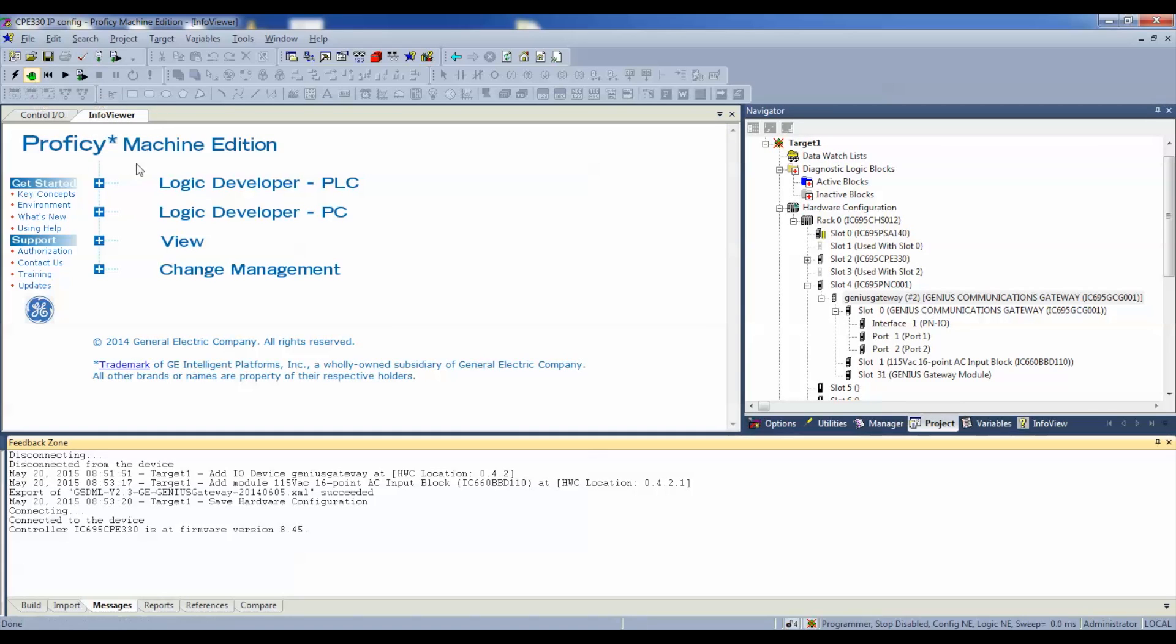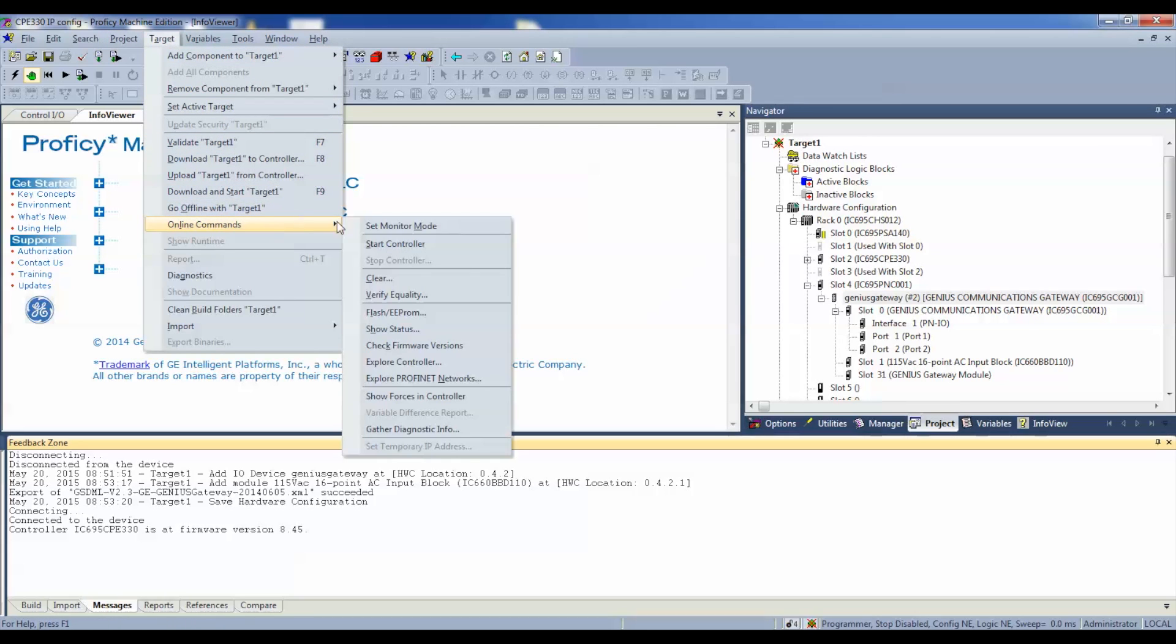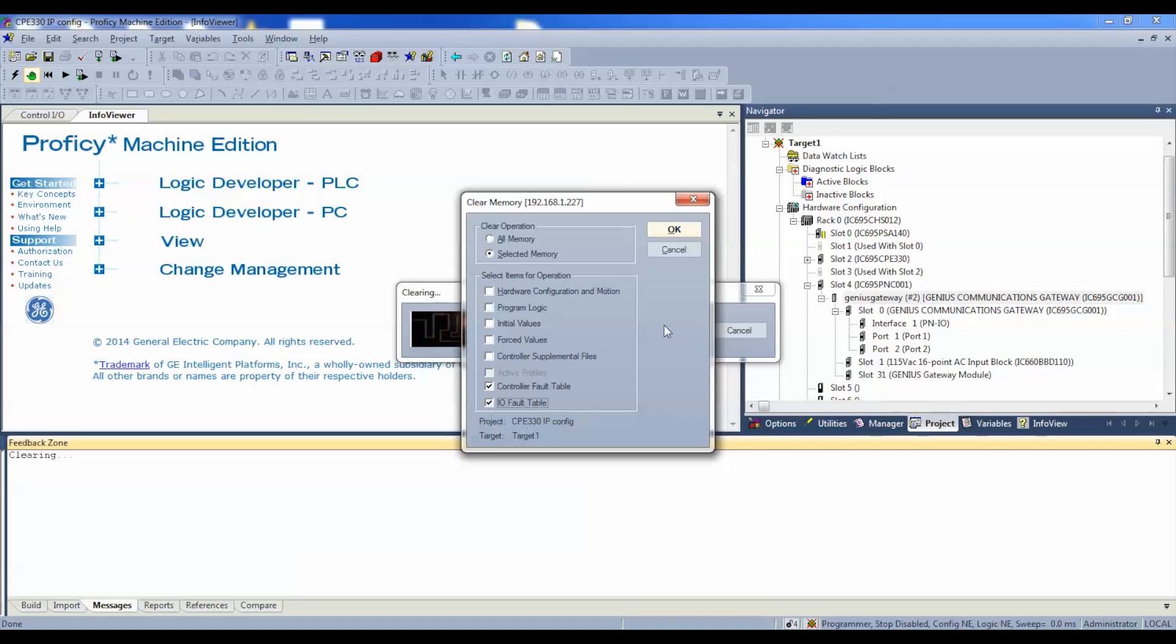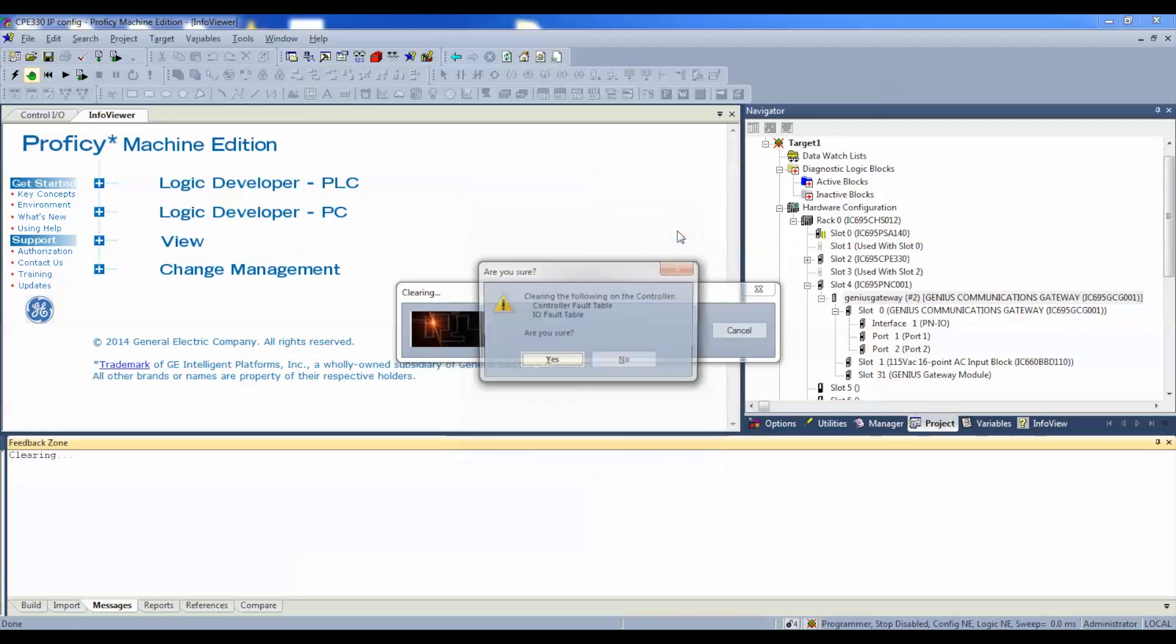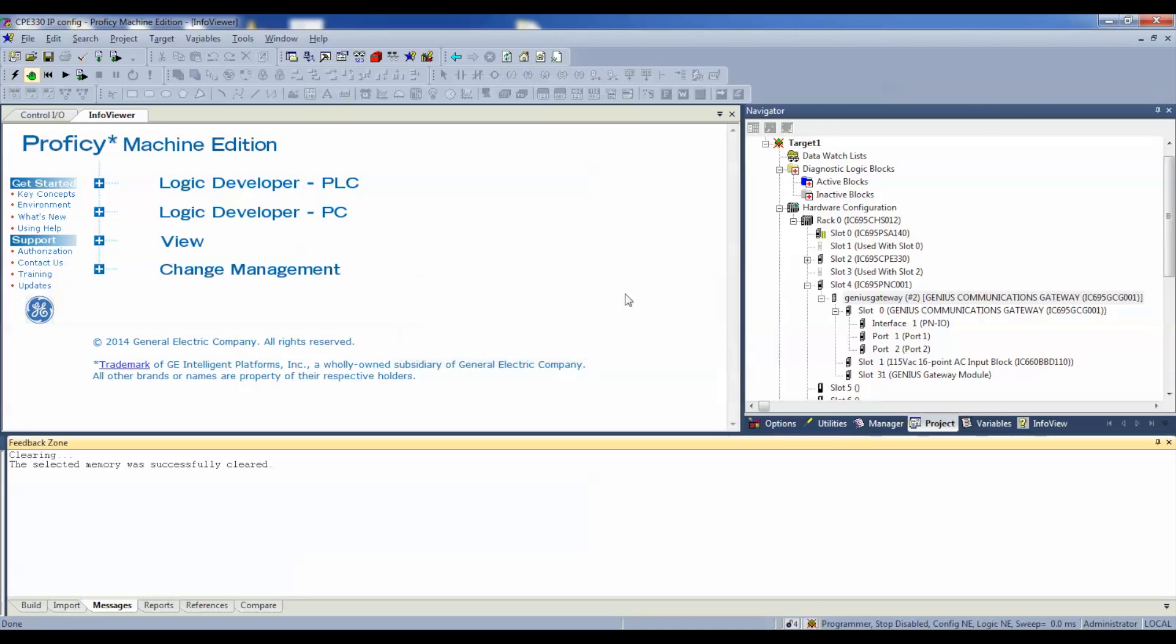Puts me in programmer mode. I'm going to go to my target, online commands. I'm going to go to clear. Now, because, now follow my arrow, the configuration and the logic are not equal. I want to do a control or an IO fault table clear, and select okay. Just those bottom two selections. It'll keep us from getting hung up when we actually do the download. Next thing is download and start active target. It's this download information with run button in one.